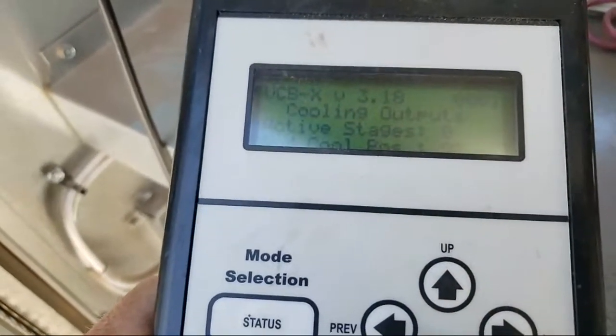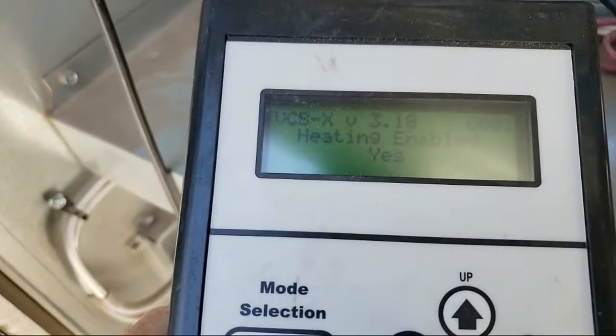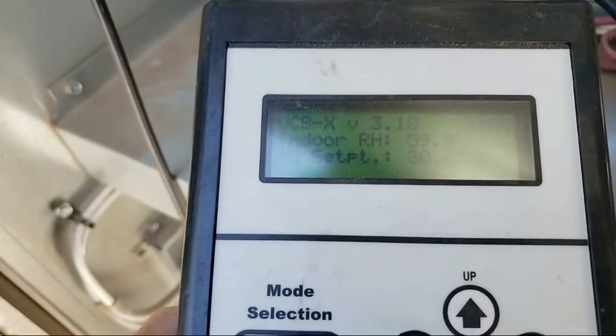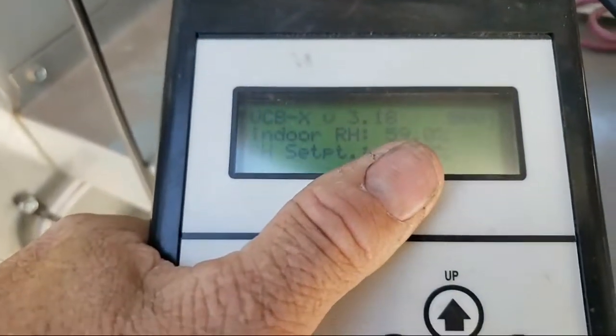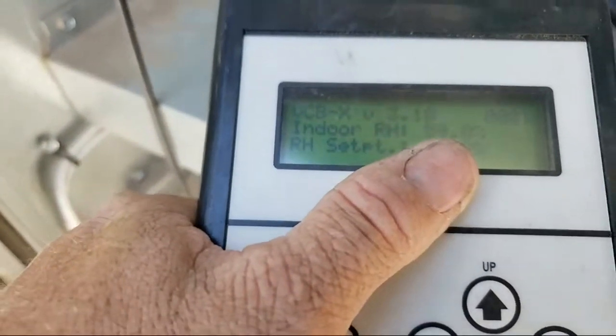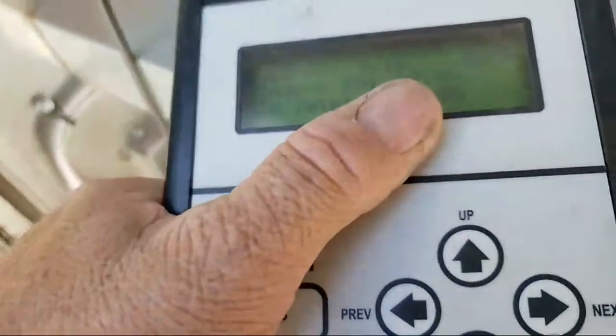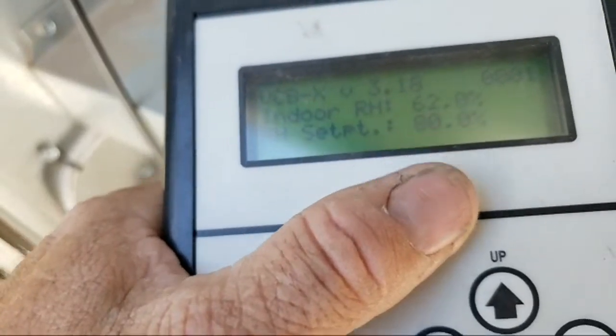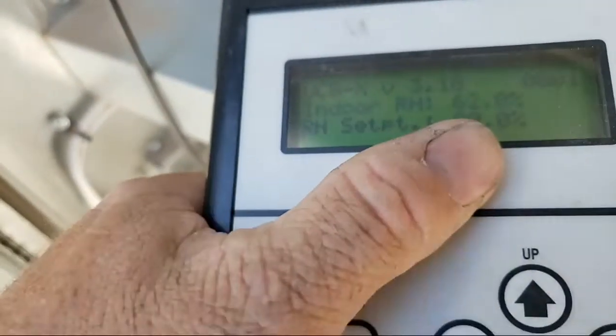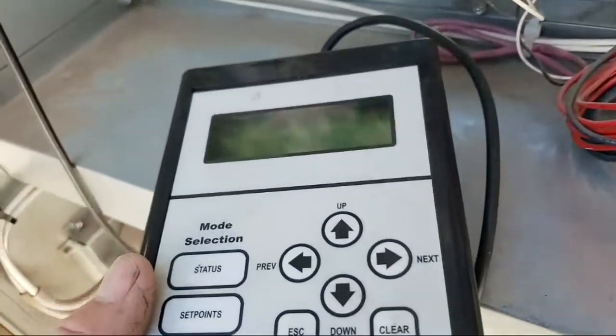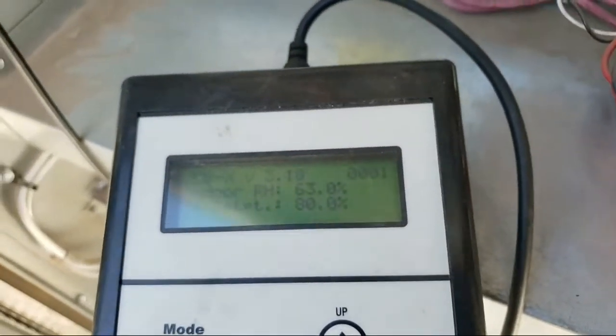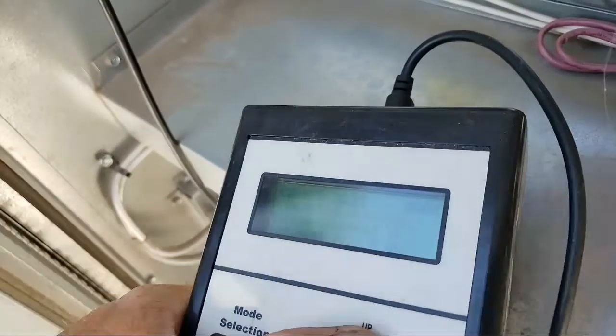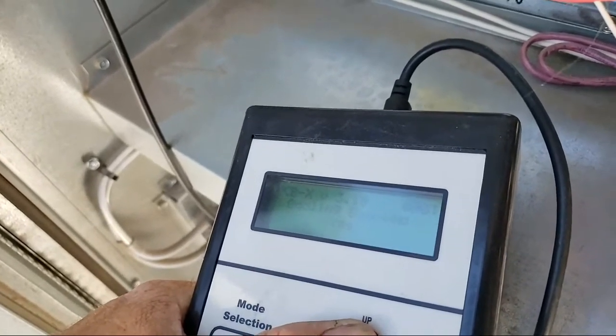But anyway, in here you have to have this tool to change settings like the enable points and the humidity set points and whatnot. Indoor relative humidity, it's dropped way down since I've let the space go from 50 something degrees up to now 68.7 degrees. So the calculation dropped way down, but the calculation was at 80% or so, and I had to kick the set point for the relative humidity all the way up to 80 just to keep it from being stuck in relative humidity reheat mode. So maybe after the monsoon season, if they ever complain about humidity in that room, which probably won't, I'll turn that back down. This is our first year of servicing these units on this site.